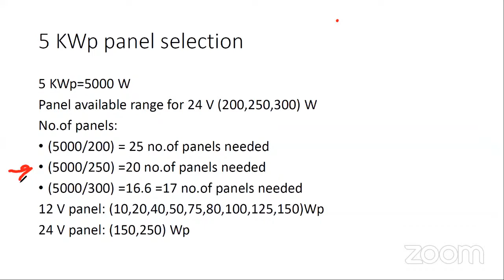Okay, so out of these 20, how we are going to connect them is the next question. As already discussed, array is how it is physically arranged, and string is how it is electrically connected. Then there's the open circuit voltage of the panel and string, the short circuit current of the panel and string, and the maximum system voltage. VOC is nothing but the voltage measured in the open circuit condition.